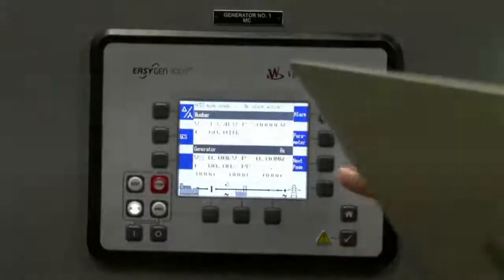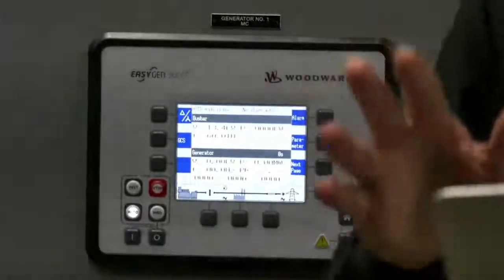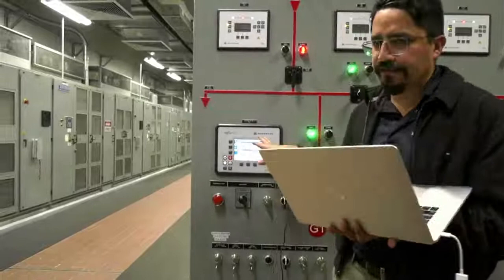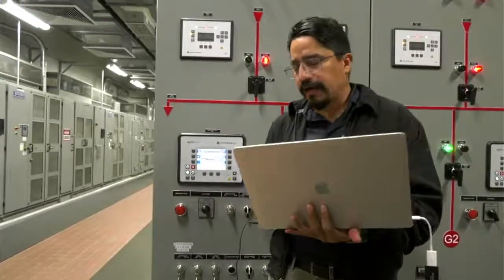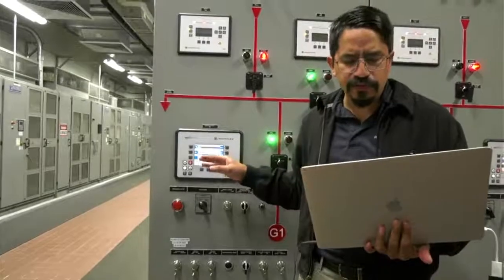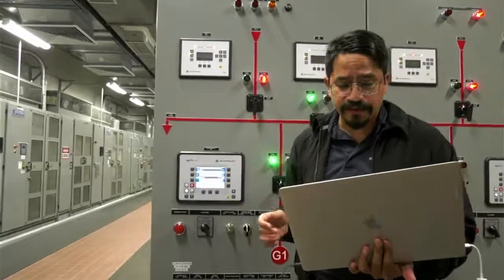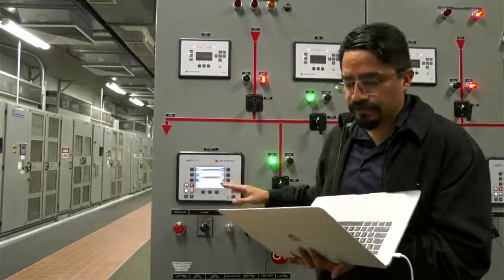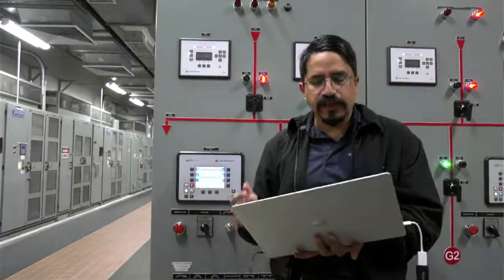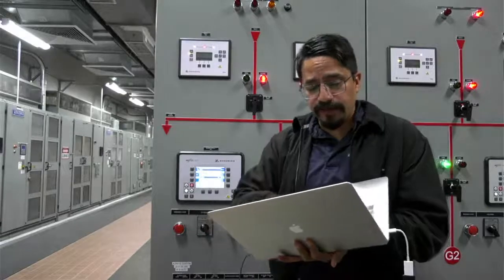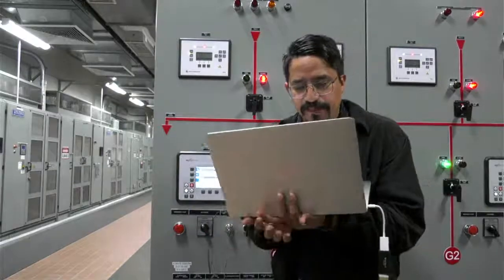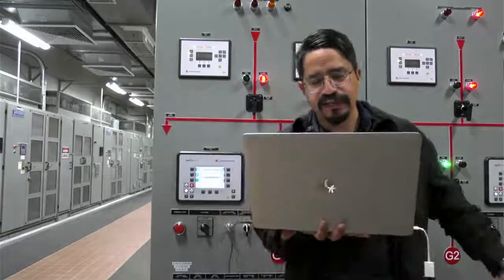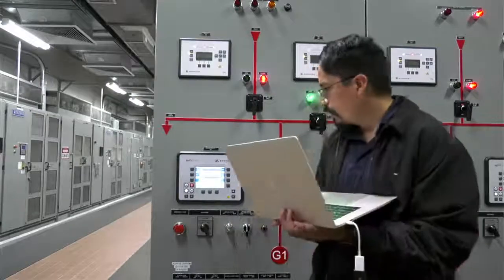All right. So EasyGens, as you know, this is going to be a different presentation. I'm just going to give an overview of the control. It's not going to be like a training for the EasyGen, but basically what the EasyGens can do. I'm reading at sheet number 4, by the way. The EasyGen can do voltage measurement, current, active power, which is kW, kVAR, which is reactive power, power factor measurement, synchronization, load sharing, and so on.